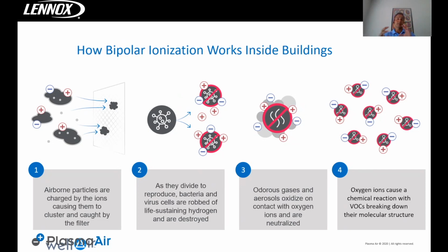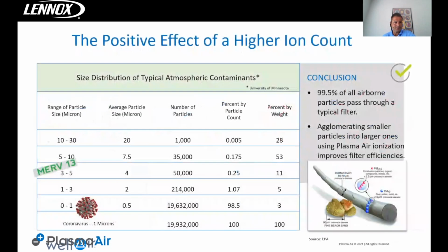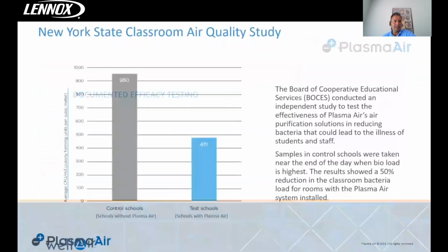We cluster it. They cluster and they get to a molecular weight or a size that they will either drop out of the breathing zone or they will get captured by a filter such as a MERV 8 or a MERV 13 filter, which under normal conditions would never be able to capture those very small particles, right? In fact, I like to say that we supercharge a simple MERV 13 filter by introducing ionization, right?